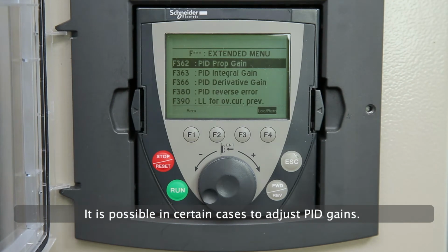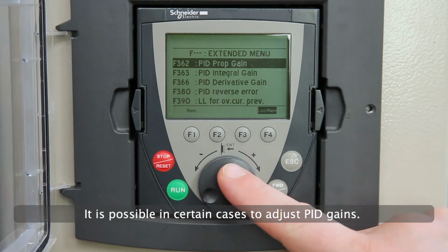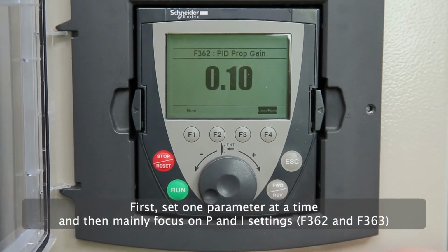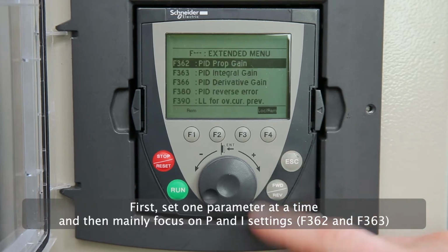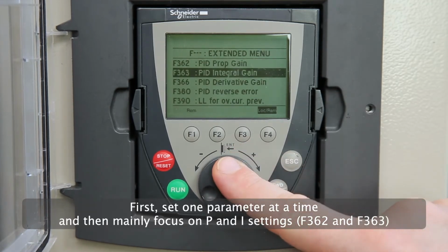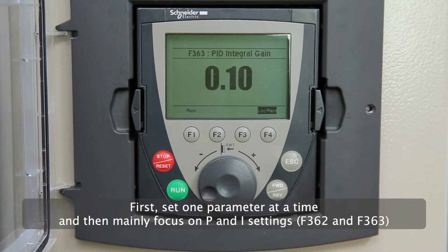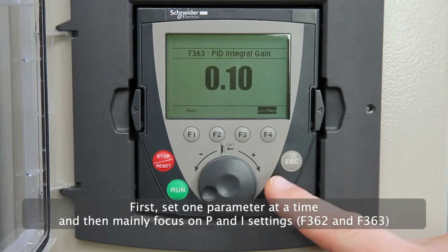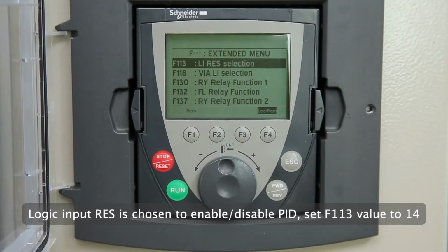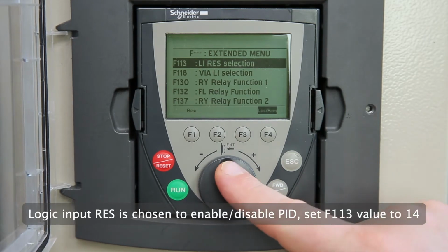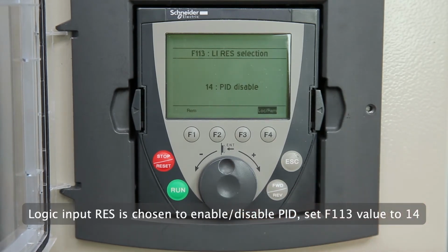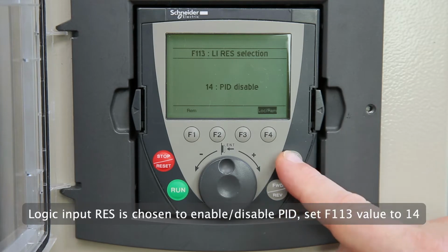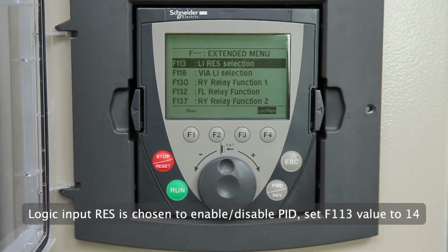It is possible in certain cases to adjust PID gains. First, set one parameter at a time, and then mainly focus on P and I settings. Logic input RES is chosen to enable/disable PID. Set F113 value to 14.